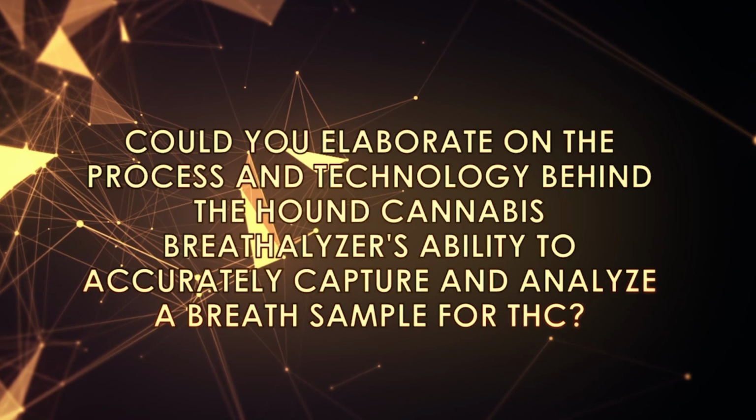So as I mentioned, we have a base station, and that base station is responsible for collecting both donor as well as air. These are the cartridges that we have. The one that I'm showing you right now is the cartridge that is used for donor collection. Now, what happens is a collector will set up this infrastructure where they will be guided through, from a base station standpoint, how to enable the collection. They will take the cartridge and provide it with a mouthpiece for the donor for a collection.